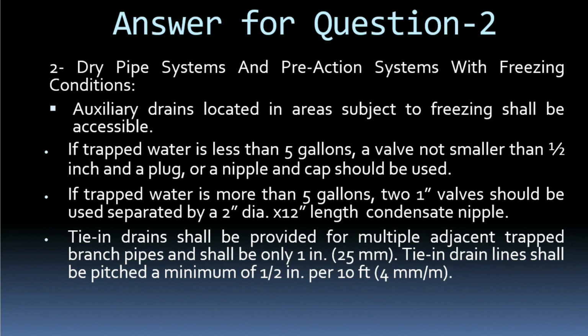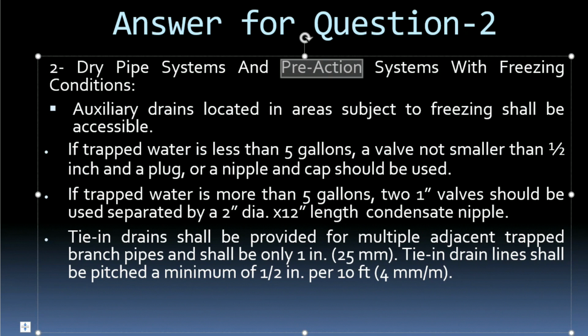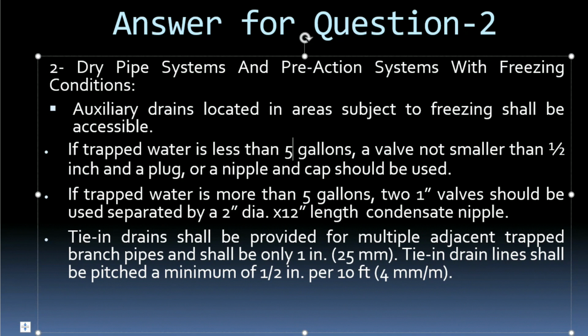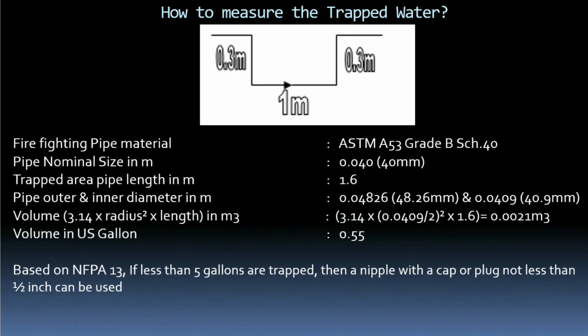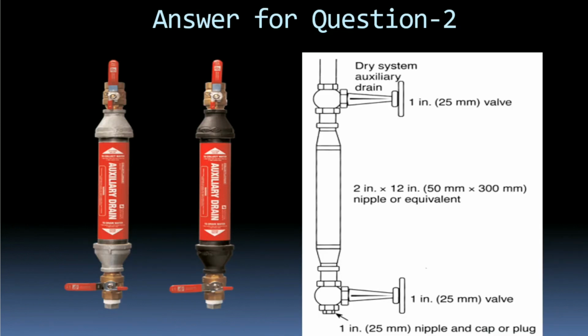And the second case is if you are going for the dry pipe and pre-action system, the auxiliary drains located in areas subject to freezing shall be accessible. First, this will be accessible, and if the trapped water is less than 5 gallons, then the valves should be not smaller than half inch. So minimum half inch valves should be used. If the trapped water is more than 5 gallons, then two 1 inch valves should be used separately. Like you see here, we have to use two 1 inch valves. This is one valve.